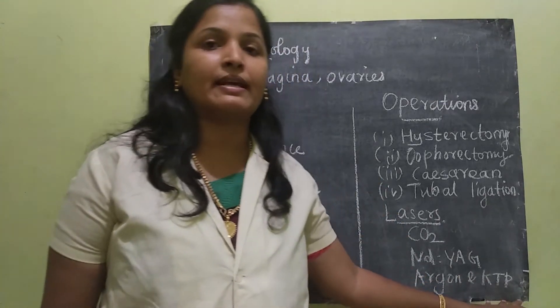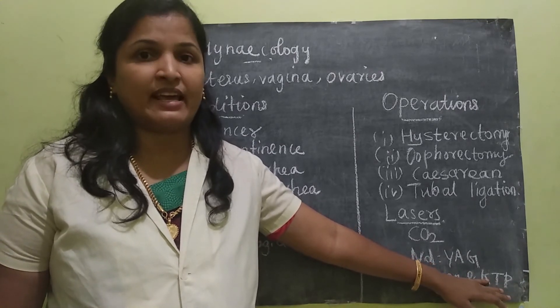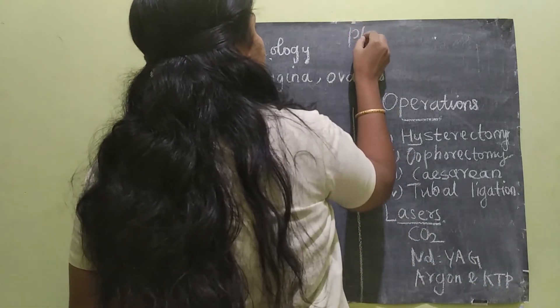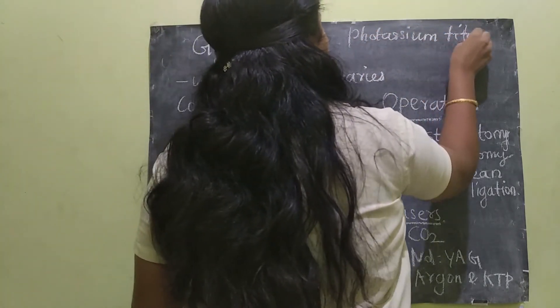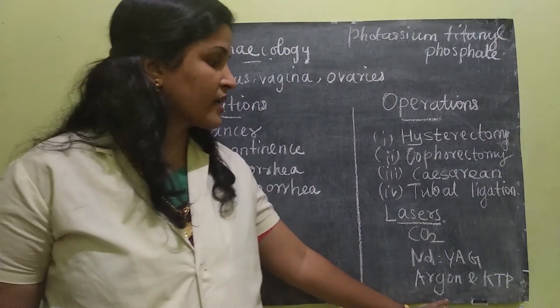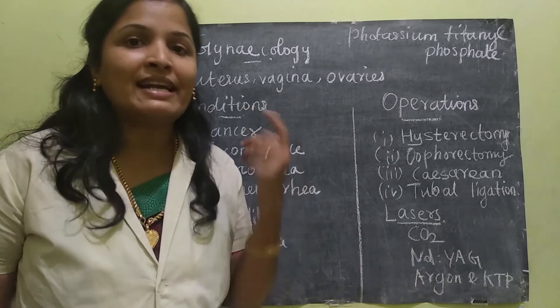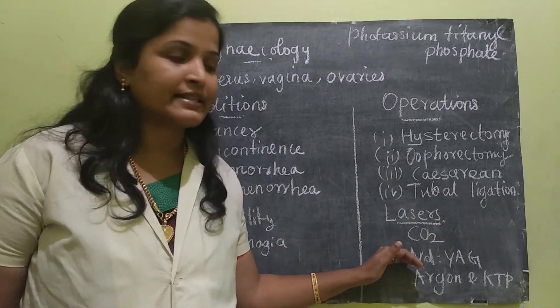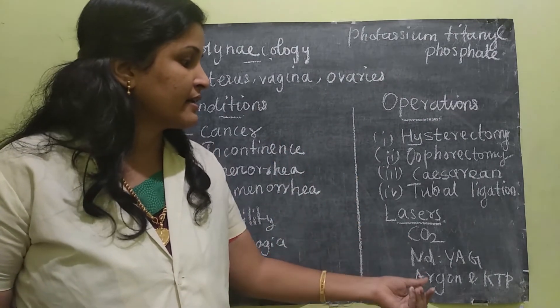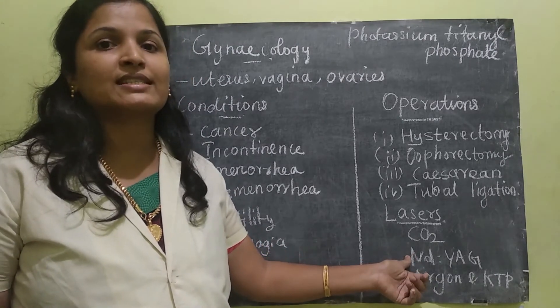The last type is the argon and KTP laser. KTP stands for potassium titanyl phosphate. Argon and KTP lasers are very similar to Nd:YAG lasers in their operations. The only difference is that while Nd:YAG acts as a deep coagulator, argon and KTP lasers are used as color-selective coagulators — meaning they are color-based.